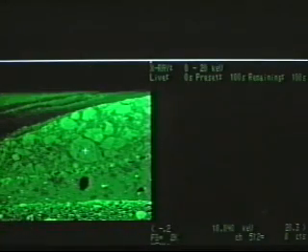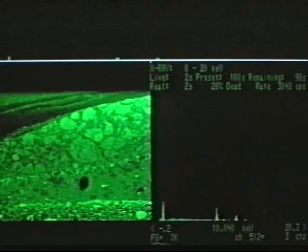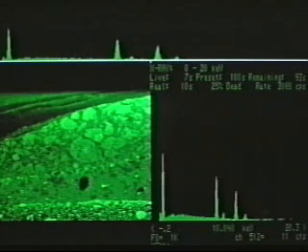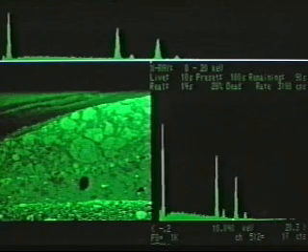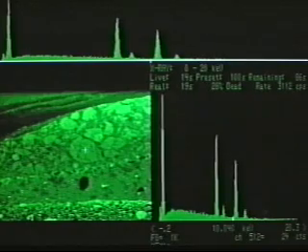First of all, a backscattered electron image gives a clear monochromatic picture of the cross-section. Then, computer technology enables the operator to move a cursor around the screen, pinpointing an area as little as 5 microns across to be analyzed by EDX, that is, energy dispersive X-ray microanalysis. This method identifies the elements within the pinpointed area by recognizing the characteristic energy of the emitted X-rays.